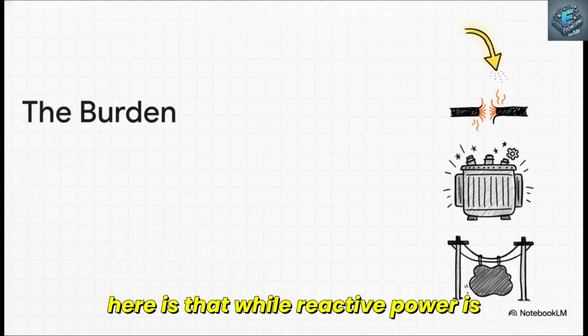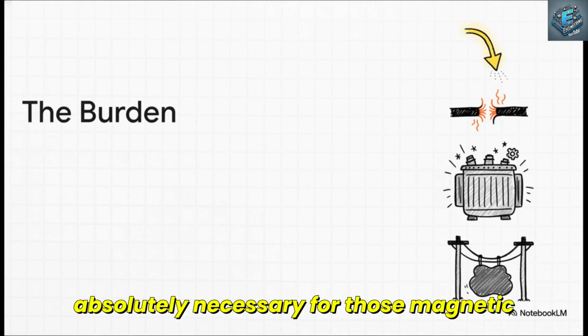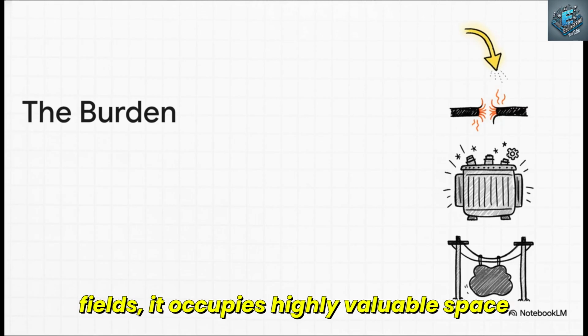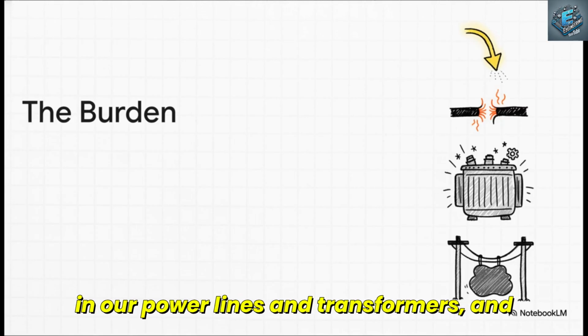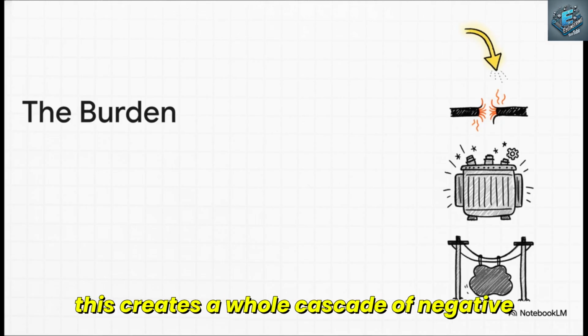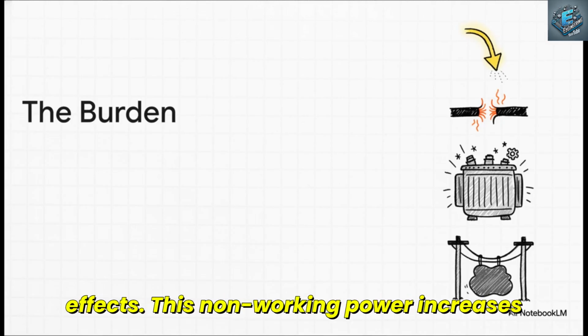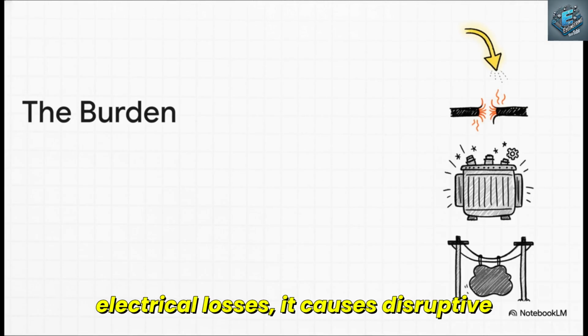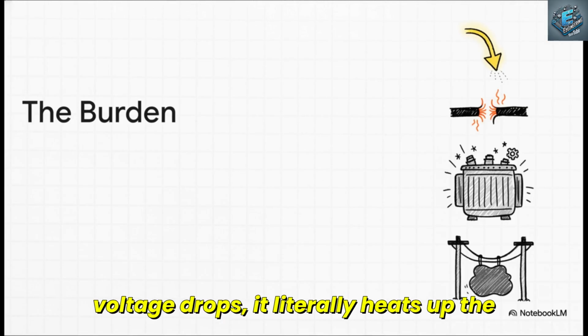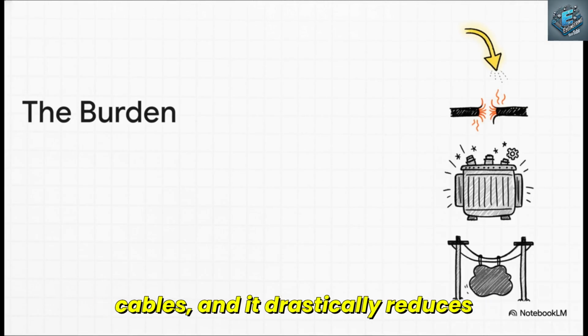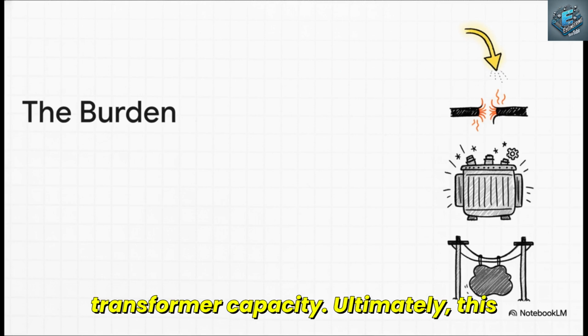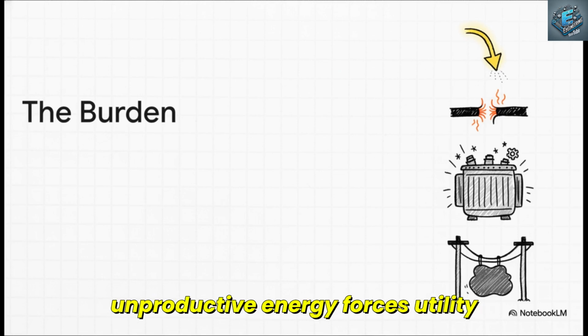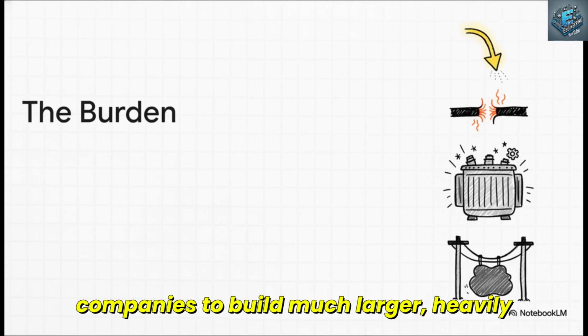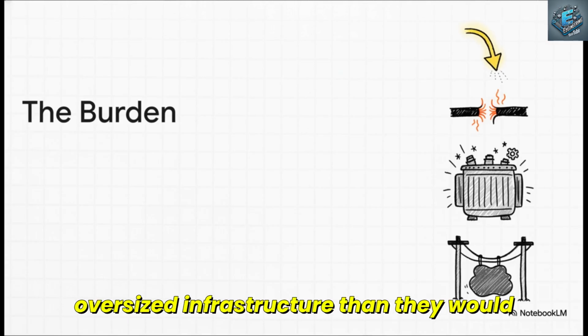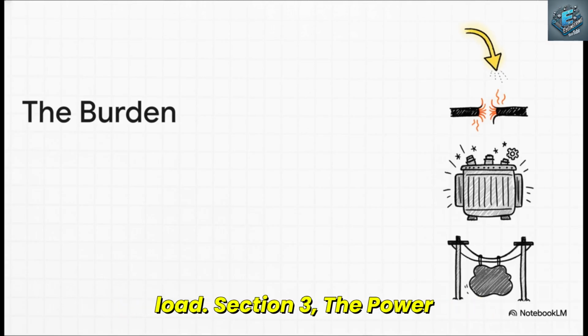So the crucial point here is that while reactive power is absolutely necessary for those magnetic fields, it occupies valuable space in our power lines and transformers. And this creates a whole cascade of negative effects. This non-working power increases electrical losses, it causes disruptive voltage drops, it heats up the cables, and it drastically reduces transformer capacity. Ultimately, this unproductive energy forces utility companies to build much larger, heavily oversized infrastructure than they would otherwise need, just to handle the extra load.